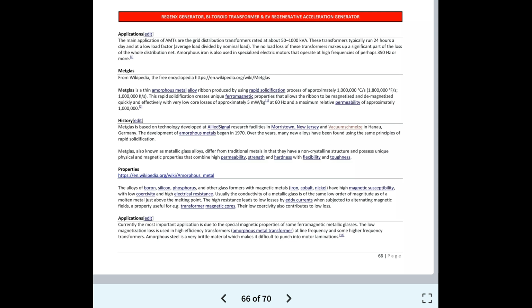Metglas. Metglas is a thin amorphous metal alloy ribbon produced by using a rapid solidification process of approximately 1 million °C/s, 1,800,000 °F/s, 1 million K/s. This rapid solidification creates unique ferromagnetic properties that allow the ribbon to be magnetized and demagnetized quickly and effectively with very low core losses of approximately 5 mW/kg at 60 Hz, and a maximum relative permeability of approximately 1 million.